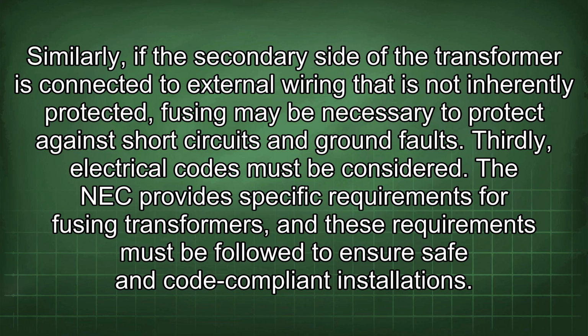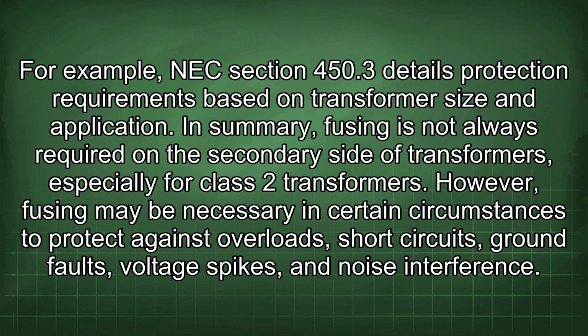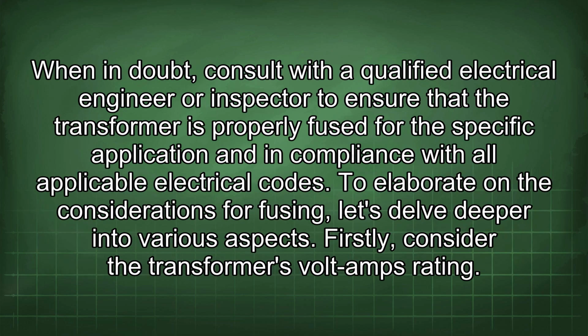Thirdly, electrical codes must be considered. The NEC provides specific requirements for fusing transformers, and these requirements must be followed to ensure safe and code-compliant installations. For example, NEC Section 450.3 details protection requirements based on transformer size and application. In summary, fusing is not always required on the secondary side of transformers, especially for Class 2 transformers. However, fusing may be necessary in certain circumstances to protect against overloads, short circuits, ground faults, voltage spikes, and noise interference. When in doubt, consult with a qualified electrical engineer or inspector to ensure that the transformer is properly fused for the specific application and in compliance with all applicable electrical codes.